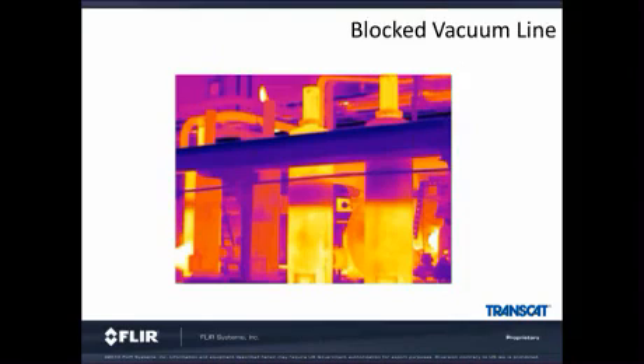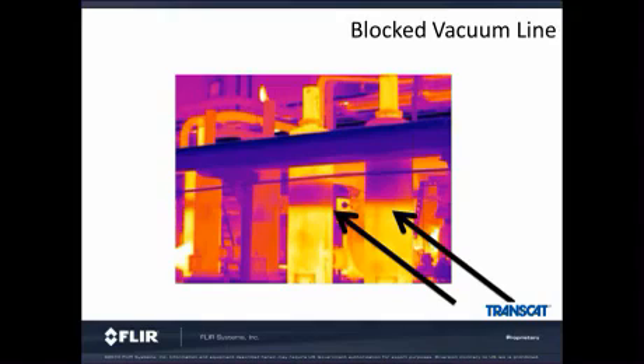Here's a unique picture of two problems on a vacuum line. The first one shows a nice cold band, indicating a blockage from both top and bottom. We can see that as the vacuum is all yellow and there's this nice purple band right in the middle. The one right next to it has a nice band across the top of the vacuum line. So that appears to have a blockage at the bottom. Again, these are targets not usually associated with a thermal camera, but can greatly benefit from access to a thermal camera.